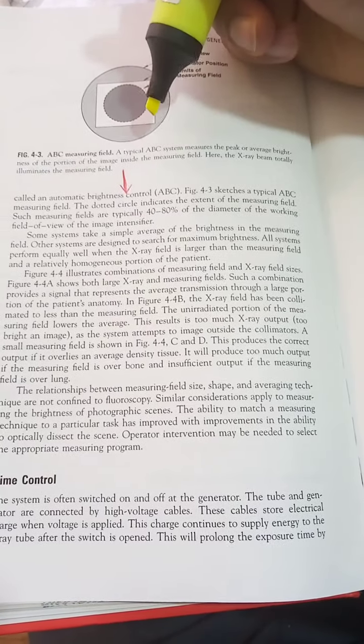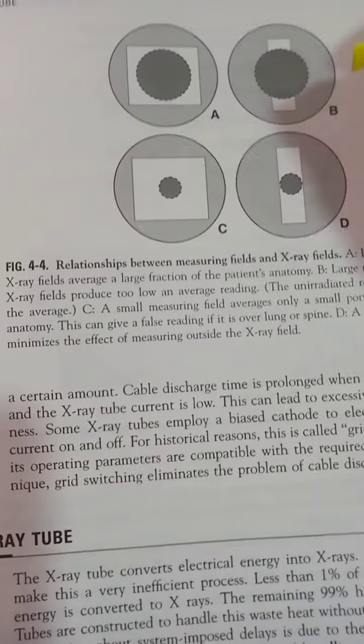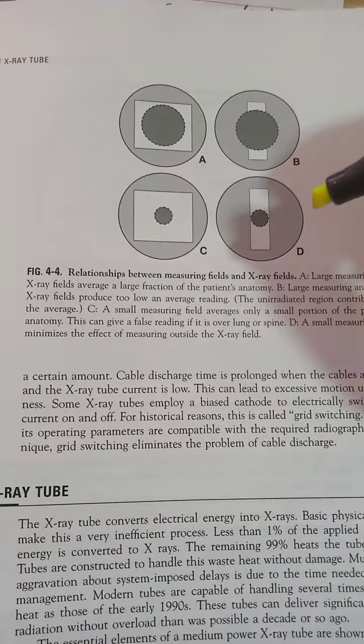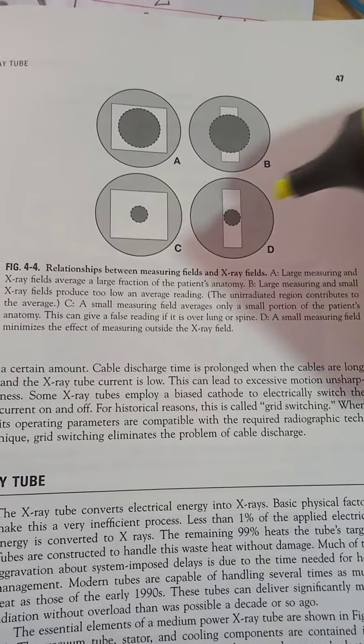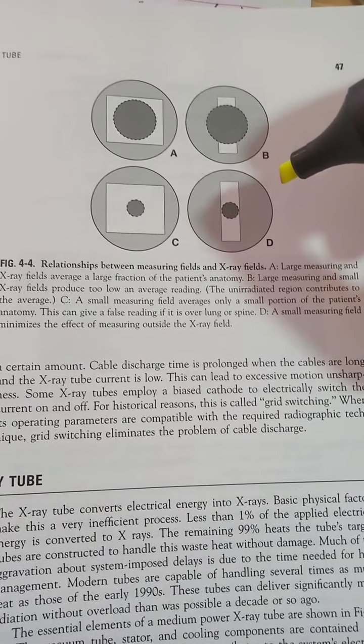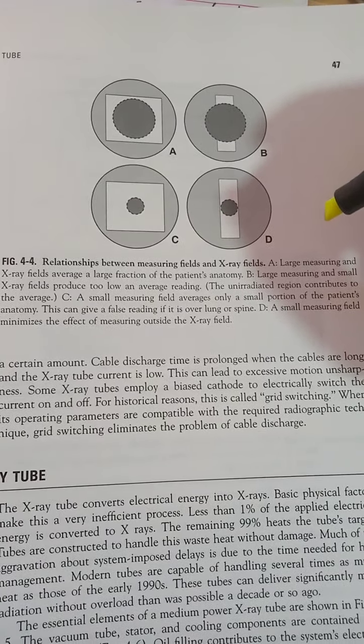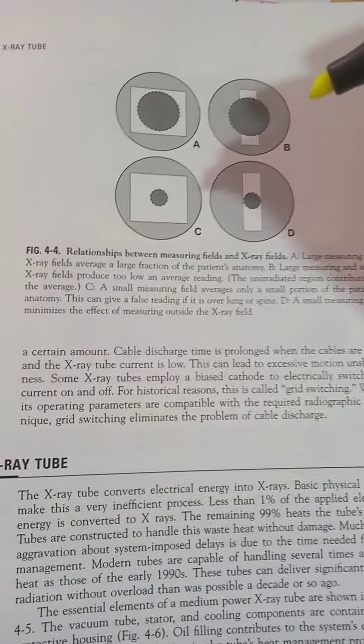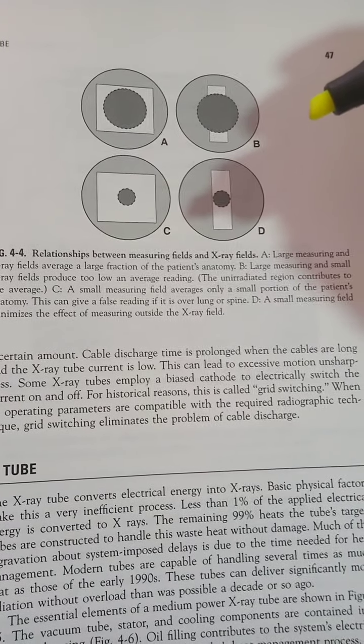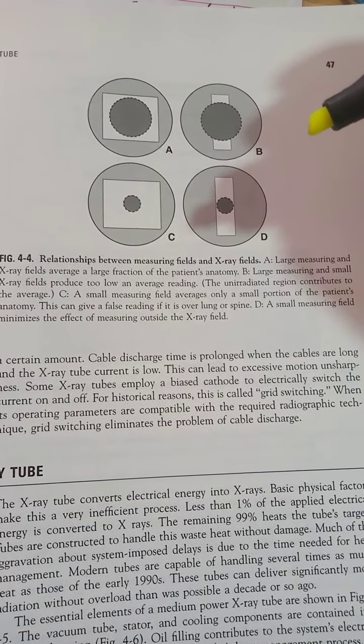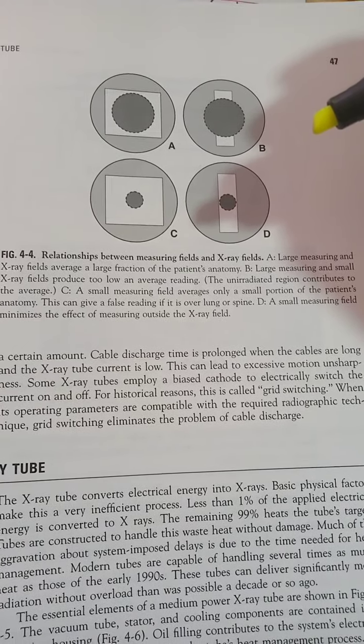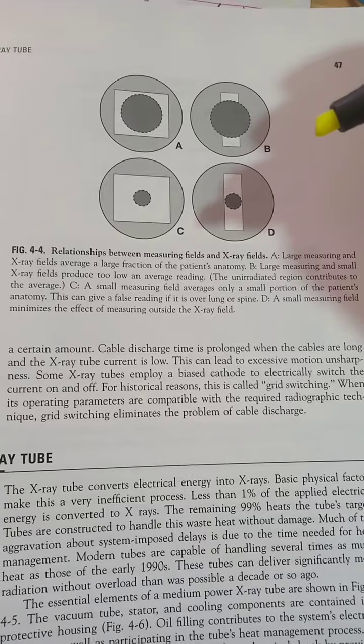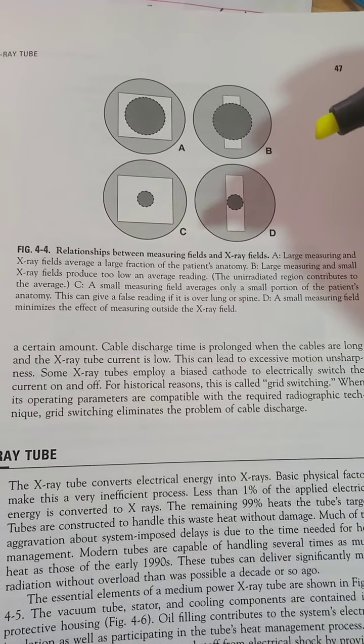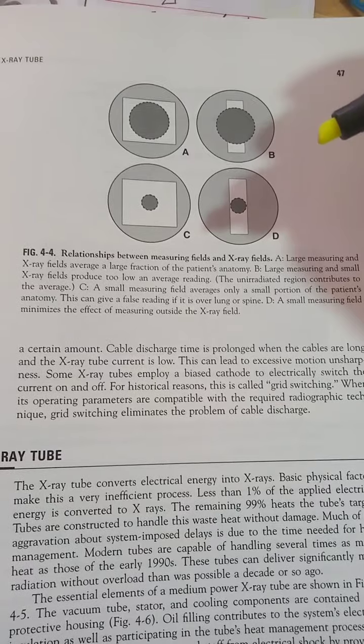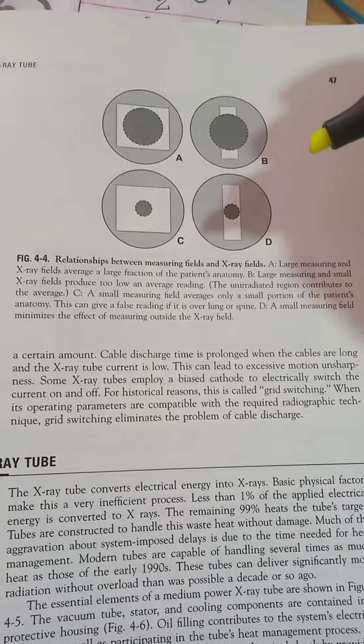The figure we've seen here is good, but it's talking about this figure now. The relationship between measuring fields and X-ray fields. Large measuring and X-ray fields average a large fraction of the patient's anatomy. A large measuring and small X-ray fields produce too low an average reading. A small measuring field averages only a small portion of the patient's anatomy. This can give a false reading, false positive, false negative. A small measuring field minimizes the effect of measuring outside the X-ray field. So we have to have a balance between the measuring field and X-ray field.